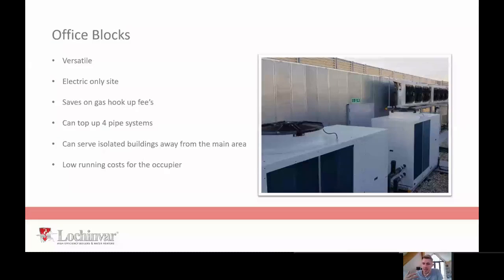Office blocks. Now we've got the ability to flow at these sort of high temperatures still incredibly effectively for hot water. If you've got a big VRV or VRF system doing your heating and cooling for the building, it seems a shame really to hook it up to some gas infrastructure to run a system, because your capex on that gas infrastructure is probably more than the heat pumps, and you end up with a system which isn't as carbon friendly. So why would you not just stick a couple of additional heat pumps on the roof to do dedicated hot water, for example?